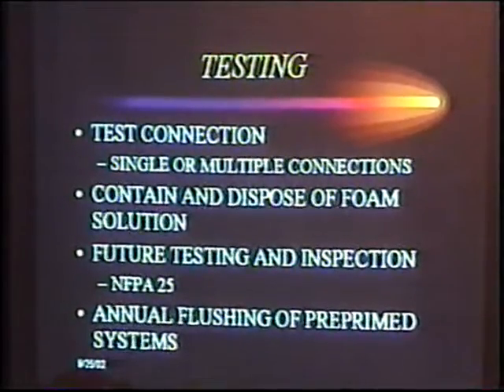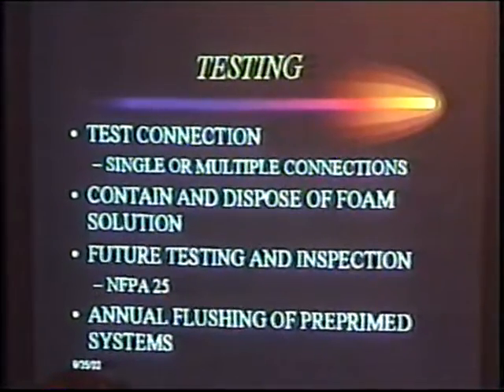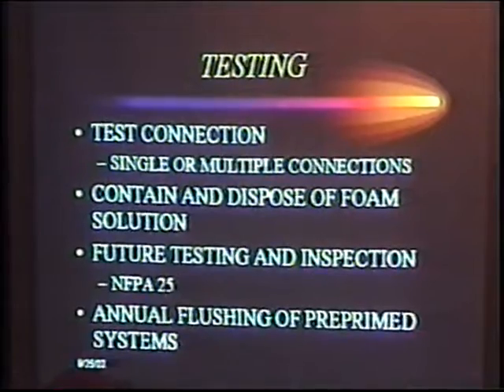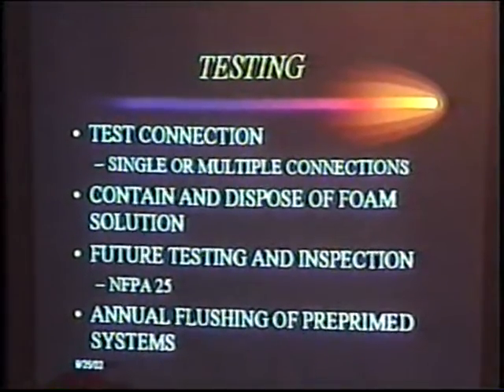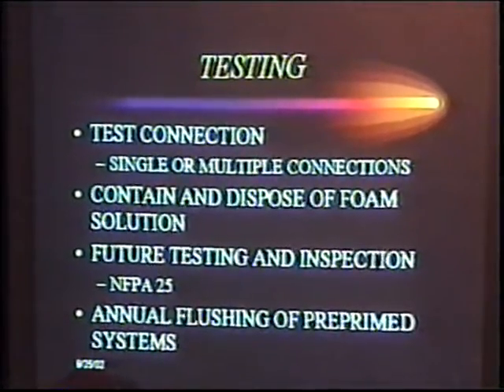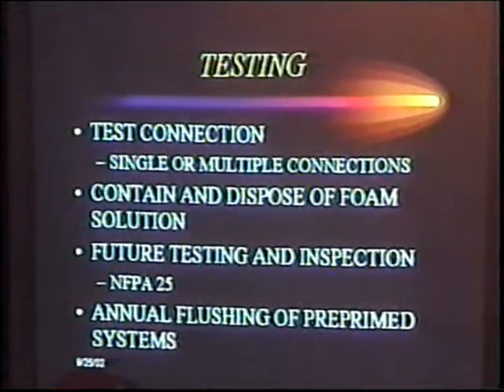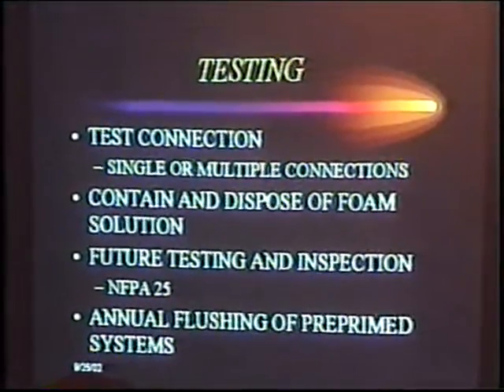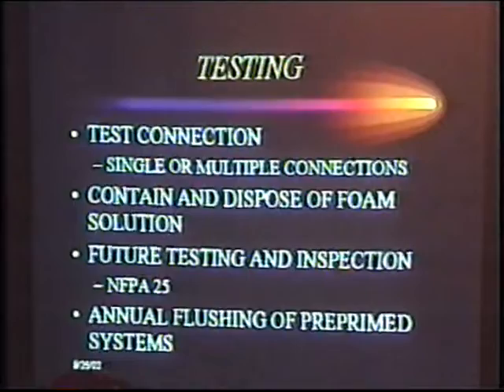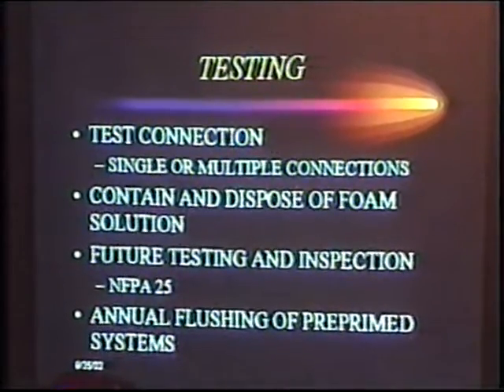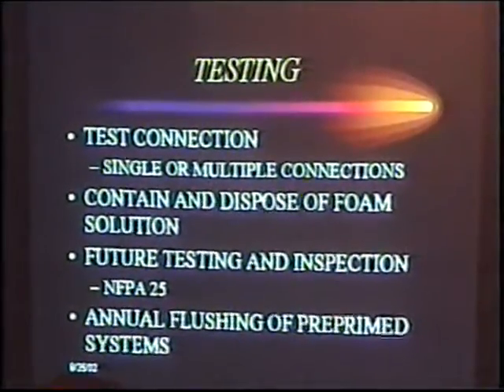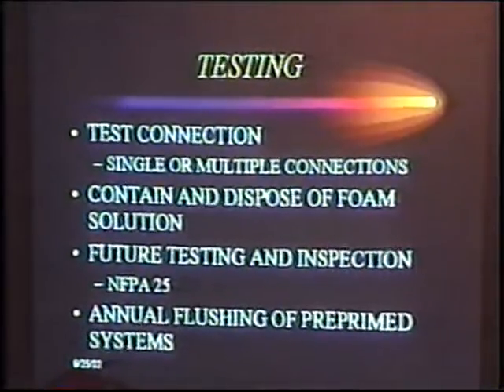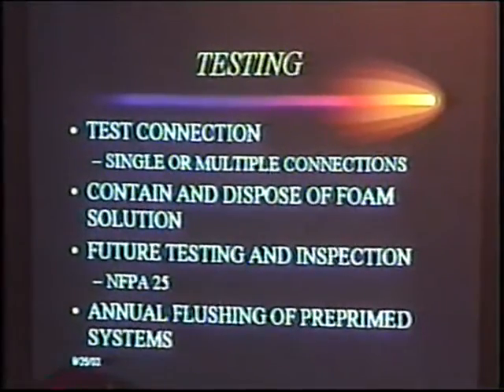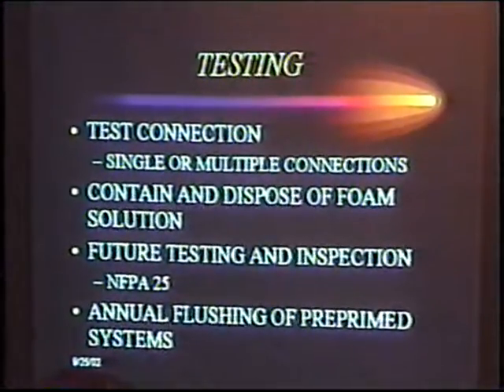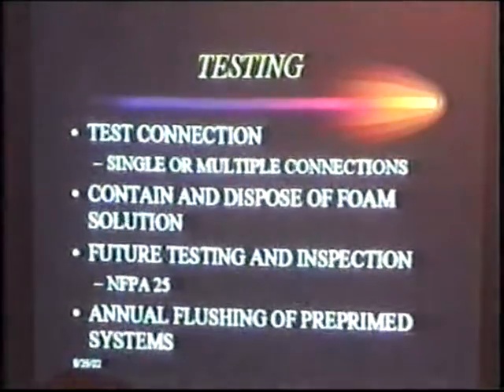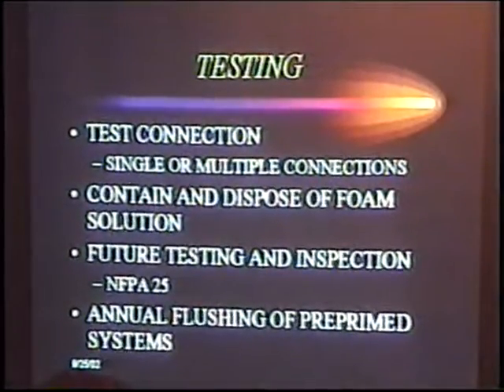Again, we talked about test connections. Usually that's going to be located just beyond the proportioner on the riser. A lot of times they'll put a block valve in the riser that they'll close for the test and then just run it right out the hose, single hose, multiple hoses, whatever you need to achieve your flow. But this is something you've got to work into your design ahead of time, knowing that you have to meet the testing requirements, and not just for the initial test. You've got to look at annual tests down the road. You've got to have something for the hoses.